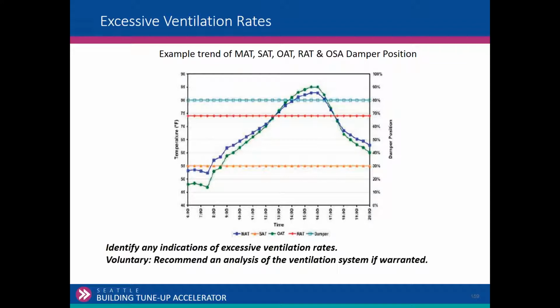Here's some trend logs, and it's kind of hard to see here, but this green line and this blue line, this is mixed air temperature and outside air temperature. So if your mixed air temperature tracks outside air temperature, what's your percentage of outside air? 100%, a lot, right? I typically wouldn't see that unless it was a 100% makeup air system or a DOAS system, something like that. So this is obviously, and well, wait a minute here, we should be bringing in 100% outside or even high ventilation rates.